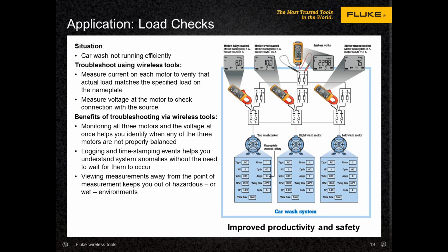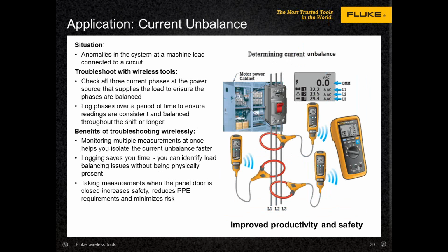You can look at how that load changes over time, and you can find those nuisance trips. Here's another common application, depending upon how loaded your situation is: current unbalance. Same with voltage unbalance, anytime you get phases on a 3-phase system that are not close together, you're going to have problems with whatever equipment is hooked up to those circuits. And today's electronic loads, like VFDs, are fairly sensitive to unbalanced conditions.